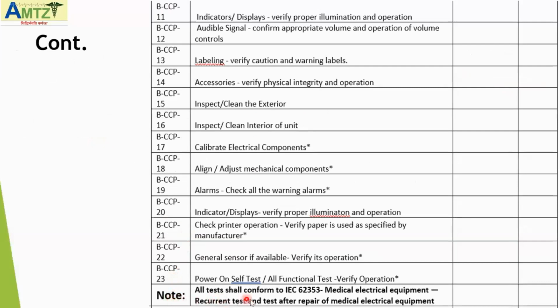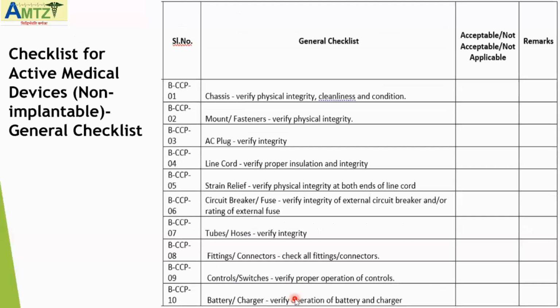All the tests shall conform to IEC 62353 standards. So this is what I was saying. If it is an active device, especially a powered device, then you have to perform this. But if it is the first category, that is a non-active device, I need not do this IEC 62353 testing at all. It is only applicable to powered devices. So this is the general checklist, or as I will call it, the common checklist for active medical devices, non-implantable.